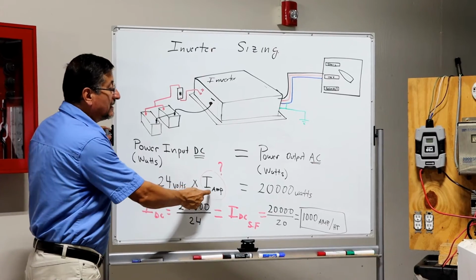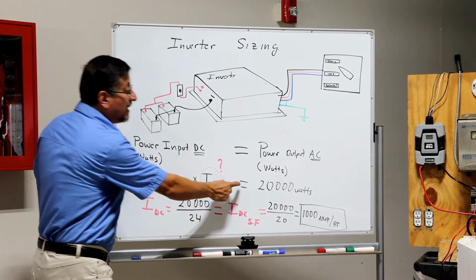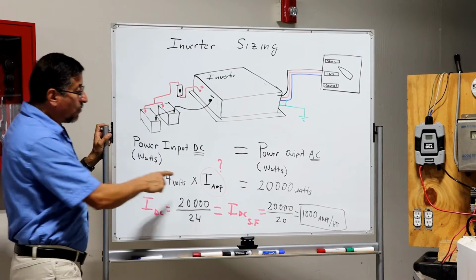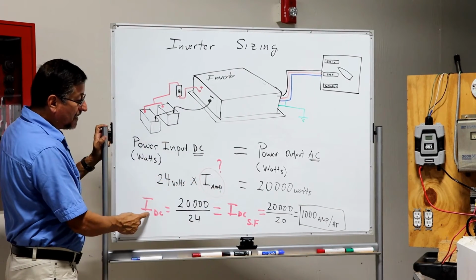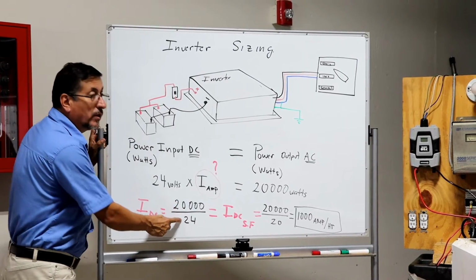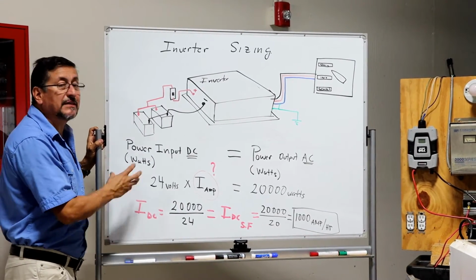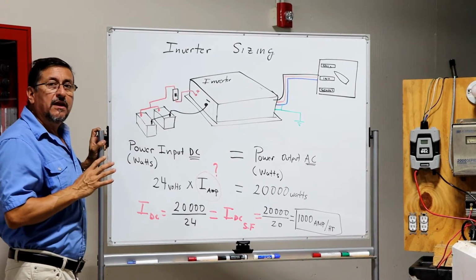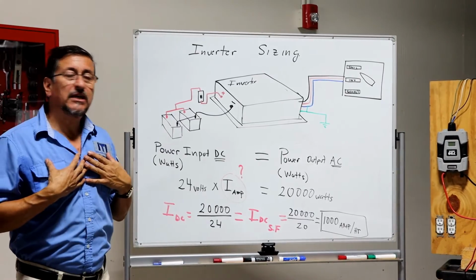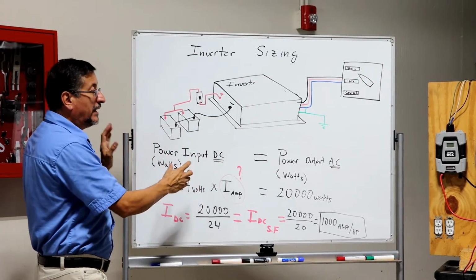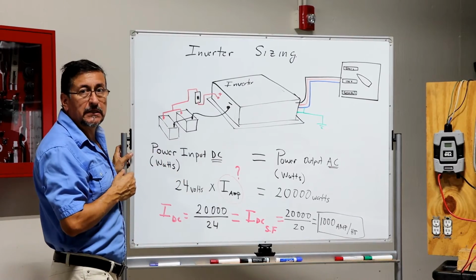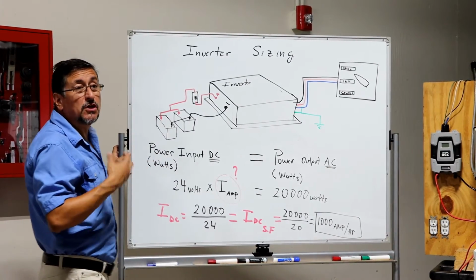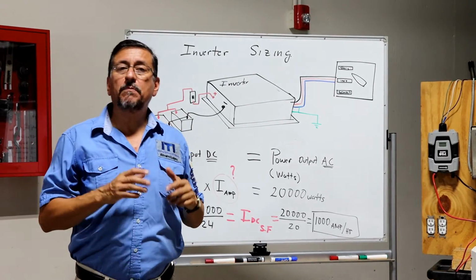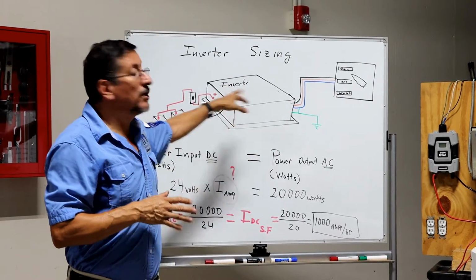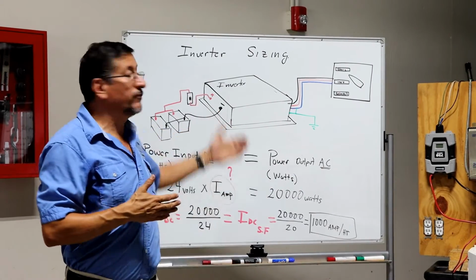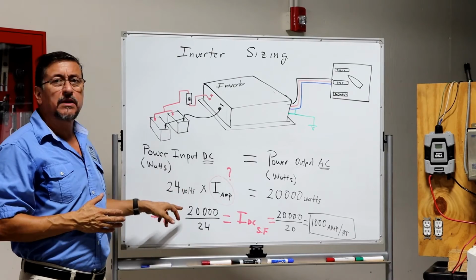24 volts times the intensity that I need in DC should be equal to 20 kilowatts. In other words, the intensity that I need in DC should be equal to 20,000 divided by 24. And this is the amount of amps that I need in my battery bank. For safety factor, the recommendation is in the input, put exactly the same as the output plus 20%, because some power is dissipated in heat, some power is dissipated in the circuit board of the computer of the inverter. For that reason, it's important to add 20%.